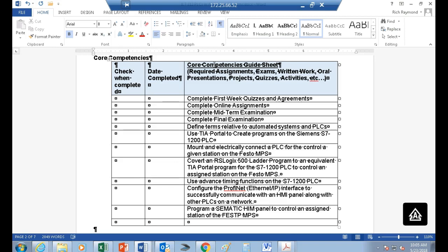We'll start by converting the ladder language over. The programs inside the Allen-Bradley don't support HMI, so we'll learn how to add that. If you're going to put another set of push buttons — even simulated ones — you have to go into your main program and add those. If you have a manual push button and an HMI simulated push button, you need to put those contacts in parallel and do an OR circuit. We'll show you how to take the Allen-Bradley program and adapt it so you can also run it with an HMI panel.